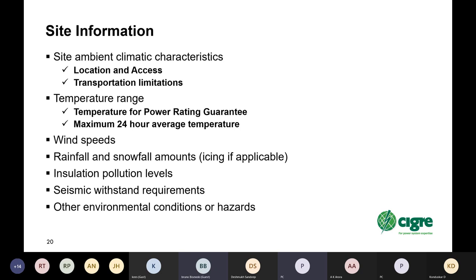So looking at site information, the main things are site ambient climatic characteristics, location and access, transportation limitations, temperature range, including the temperature for power rating guarantee, maximum 24-hour average temperature for lifetime calculation of transformers and hotspots, wind speeds, rainfall and snowfall amounts, including monthly, yearly, and 1 hour, 3 hour amounts, so that the site drainage can be designed. Insulator pollution levels, seismic withstand requirements, and any other environmental conditions or hazards that need to be covered in the design.